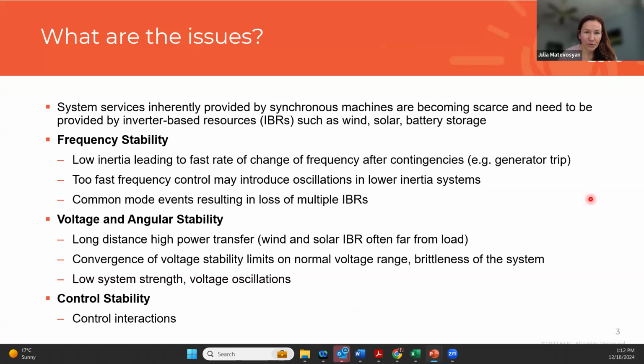Too fast frequency control, that grid following inverter-based resources can provide very well, but it may introduce oscillations, especially in low inertia systems. And then there may be common mode events that could potentially result in multiple inverter-based resources tripping simultaneously. And this may lead again to frequency events that have not been seen before, where you had fewer synchronous machines and they had no common mode tripping behavior, maybe.